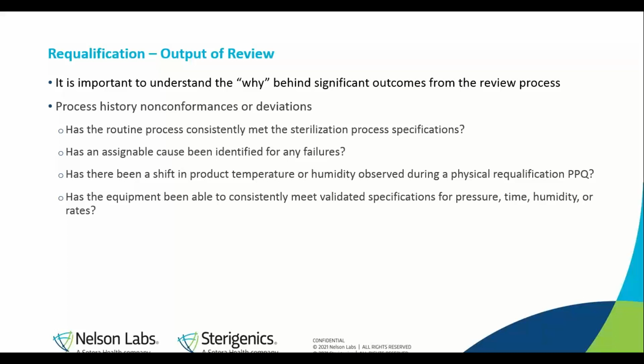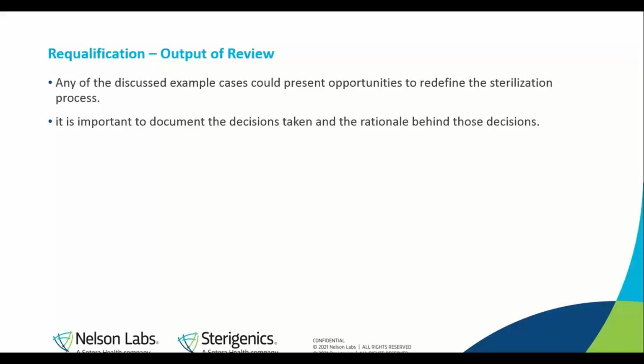Lastly, the output of the review may identify that there's a high number of process history nonconformances or deviations. Some questions to ask about this are, has the routine process consistently met the sterilization process specification? Especially, have any assignable causes been identified for any failures? Has there been a shift in product temperature or humidity observed during any physical requalification PPQ? Has the equipment been able to consistently meet the validated specifications for pressure, time, humidity, or rate? Any of these discussed example cases could present opportunities to redefine your sterilization process. As mentioned earlier, it's important to document the decisions taken and the rationale behind those decisions to keep with your validation master file.